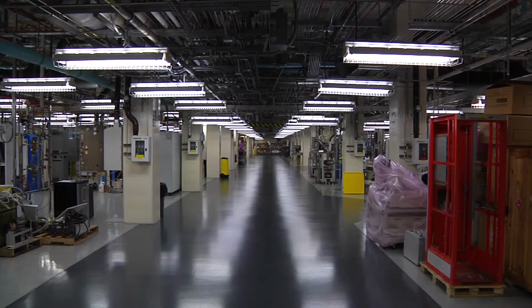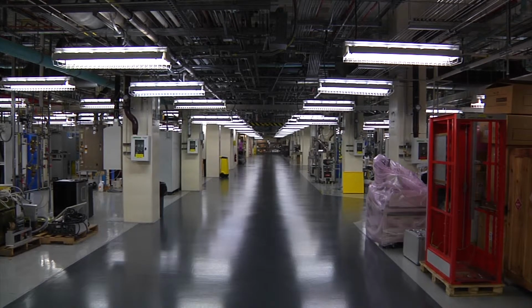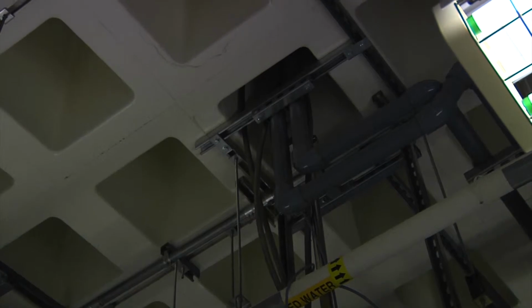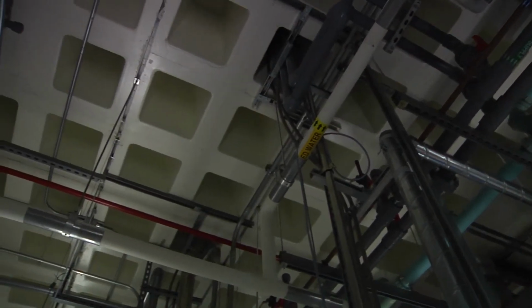The subfab is the area below the clean room. Clean rooms are also called fabrication facilities, or fab for short, so the subfab is the below fab area. One of the important factors of a subfab is it is not in the clean air path. The air goes through the clean room floor, but there's another layer of decking below that. That's a concrete, what we call a waffle slab. The air goes below the clean room floor, but above the waffle slab, so the subfab is completely isolated from the clean room itself.